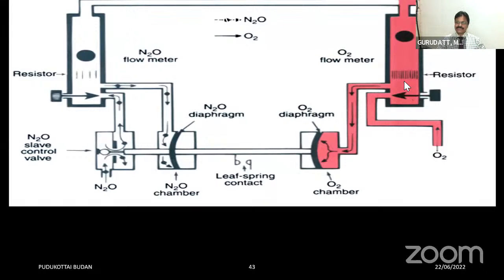Once you open oxygen, the oxygen flows into this oxygen chamber. Because of the pressure in the oxygen chamber, the shaft is pushed towards the nitrous oxide, and the nitrous oxide slave control valve will open, and only then does the nitrous oxide start flowing into the flow meter. And this proportion of a minimum of 25% is always maintained. If you try to increase the nitrous oxide, the shaft starts moving towards oxygen, and the nitrous oxide flow automatically starts reducing. That's how the proportioning device of the ORMC works.